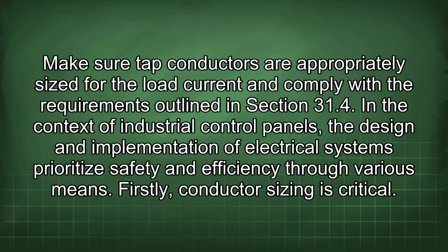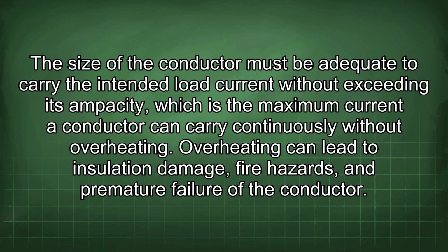In the context of industrial control panels, the design and implementation of electrical systems prioritize safety and efficiency through various means. Firstly, conductor sizing is critical. The size of the conductor must be adequate to carry the intended load current without exceeding its ampacity, which is the maximum current a conductor can carry continuously without overheating. Overheating can lead to insulation damage, fire hazards, and premature failure of the conductor.